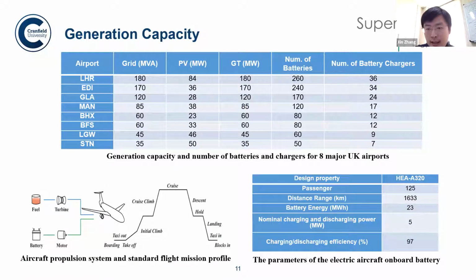Once we got this data, based on our mathematical modeling we could decide the generation capacities within these 8 UK airports. For example, the PV generation capacity, based on land availability, was calculated across the 8 airports, together with the gas turbine size and the number of batteries and battery chargers. Those are fixed per airport but differ across different airports.